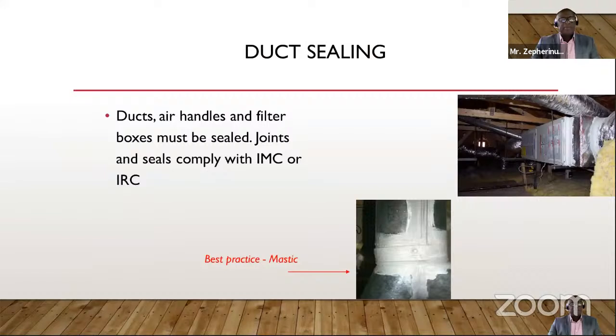Duct sealing. The ducts, air handlers, and the filter boxes must be sealed. The joints and seals must comply with the International Mechanical Code or the International Residential Code. So the code references other standards and other codes as well. And so no code really stands alone. There are references to other codes and other standards. So for example, the duct, if you have a very efficient cooling system, but your ducts are not sealed properly, you can be losing conditioned air through the joints.